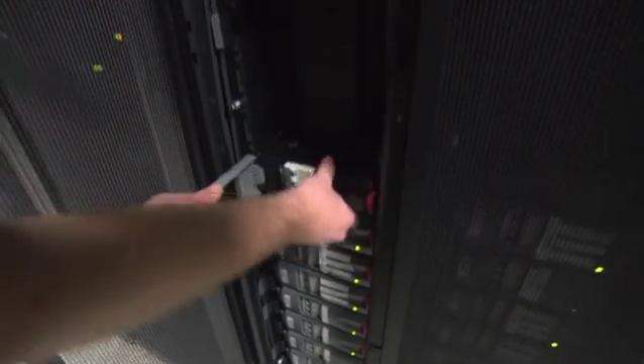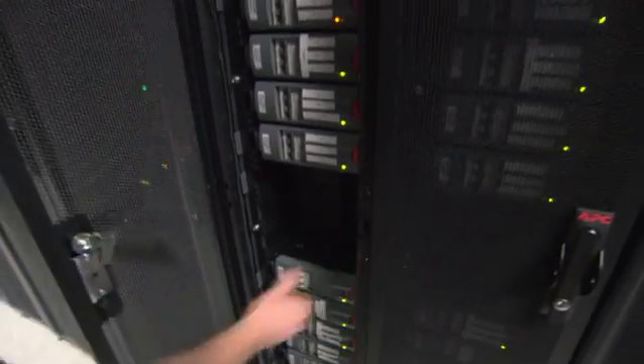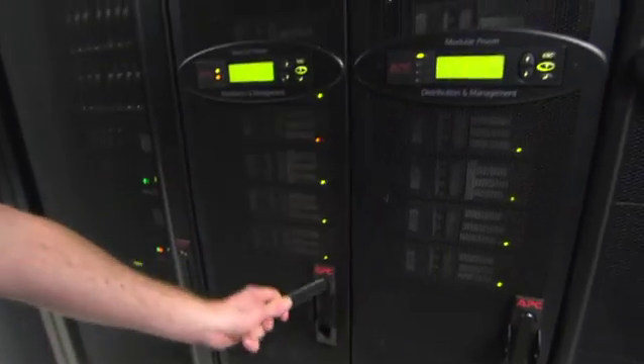With the 277kW PDU any one of my engineers can just go down there, plug a whip in and it's really flexible. We can get 16 amp, 32 amp and the other great thing is it's got built-in monitoring.